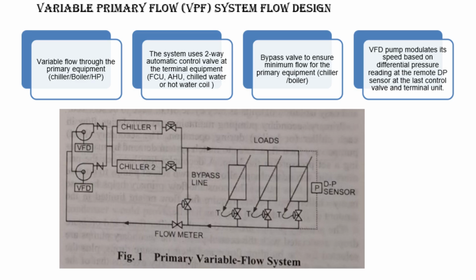In a variable primary flow, or VPF system, both the primary equipment and the distribution loop experience variable flow. This design allows the system to efficiently match pump energy and equipment operation with real-time load demands. Let's break down how it works.